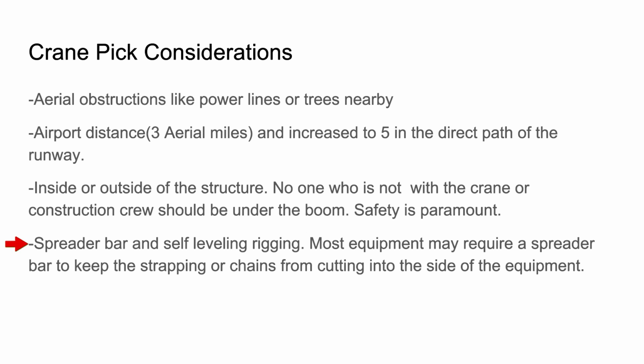Spreader bars are something guys sometimes don't think about, but if you're carrying something pretty heavy, you don't want those straps impinging on the sides, that's where you'll get closed doors and stuff. The idea of spreader bars is to have them wider than whatever piece of equipment you're flying. A lot of that depends on weight, and a lot of it's common sense. If you're thinking, if I put straps on this thing and picked it up, is that going to bend everything, then you need spreader bars. If you're picking up a 2-ton condenser, you probably don't need it. If you're picking up a 30-ton RTU, you probably do.